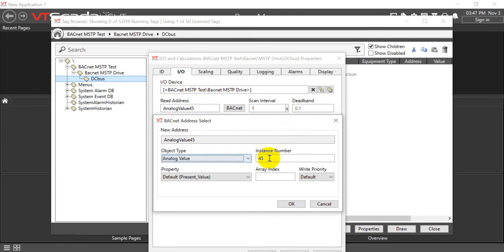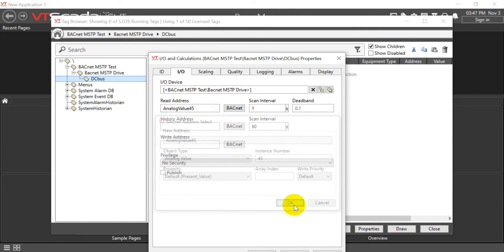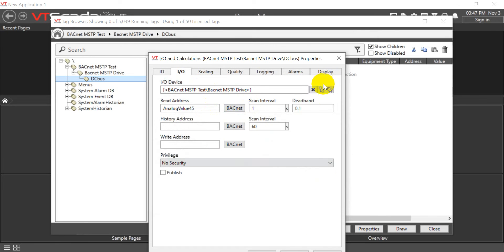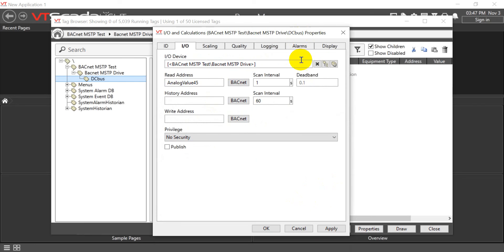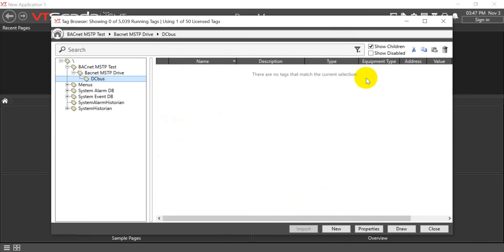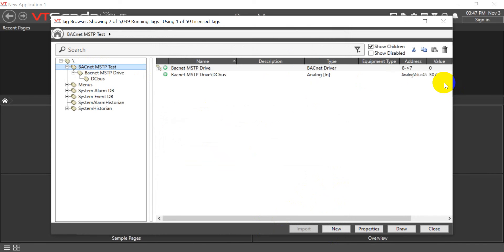So here, assign 45 - this one is DC bus voltage. After setting this one, we can check it can read the DC bus value from BACnet MSTP and show on VT SCADA successfully. That's all for today's topic. Thank you.